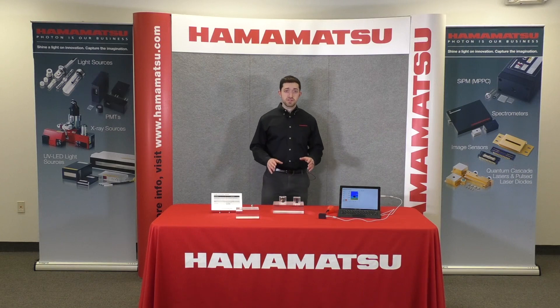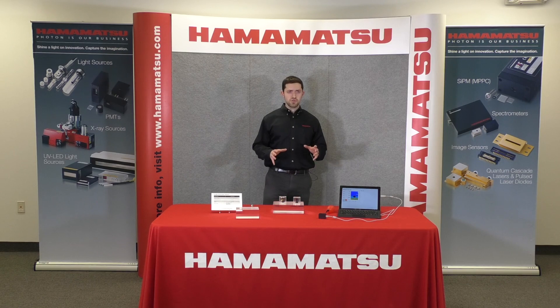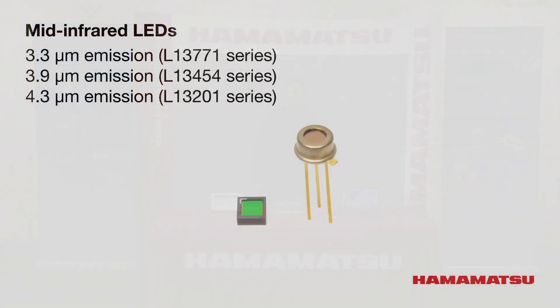So enough about detectors. I'd like to talk about our LEDs. Typically in the infrared region you're constrained to thermal sources or even a QCL, but the LED can be an extremely cost-effective solution. We have three LEDs available: one for methane at 3.3 micron, one for reference at 3.9 micron, and another for CO2. These match up perfectly with the filters we have available. LEDs offer very low power consumption, very long lifetimes, and high output at the center wavelength. We also have different packages available in can and ceramic, which can offer even more cost-benefit solutions.